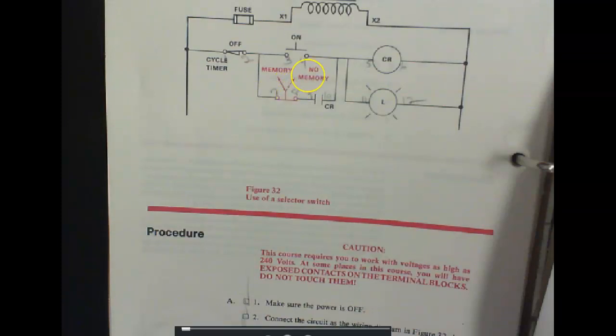If I put this into the no memory or jog position, it's going to open this contact right there, and what I've done is I've taken away the sealing circuit. So now when I press the start button, the CR will come in, but this contact's going to close, but there's no circuit, right? You understand? When I let it go, it's going to cut off, so every time we press it, CR is going to come in, every time we let it go, CR is going to drop out.